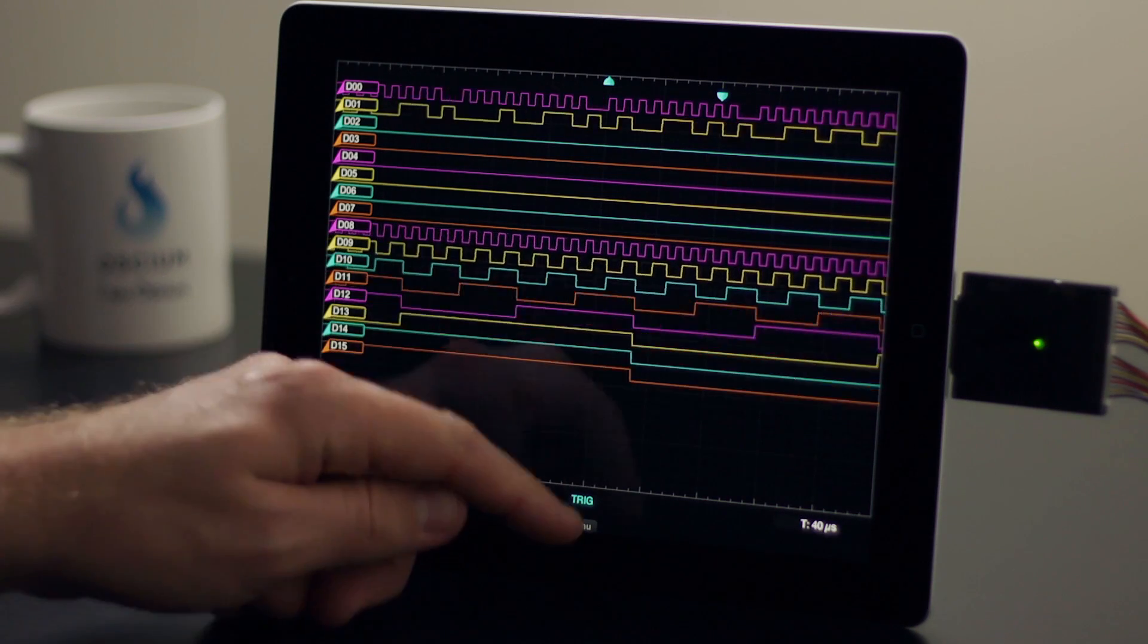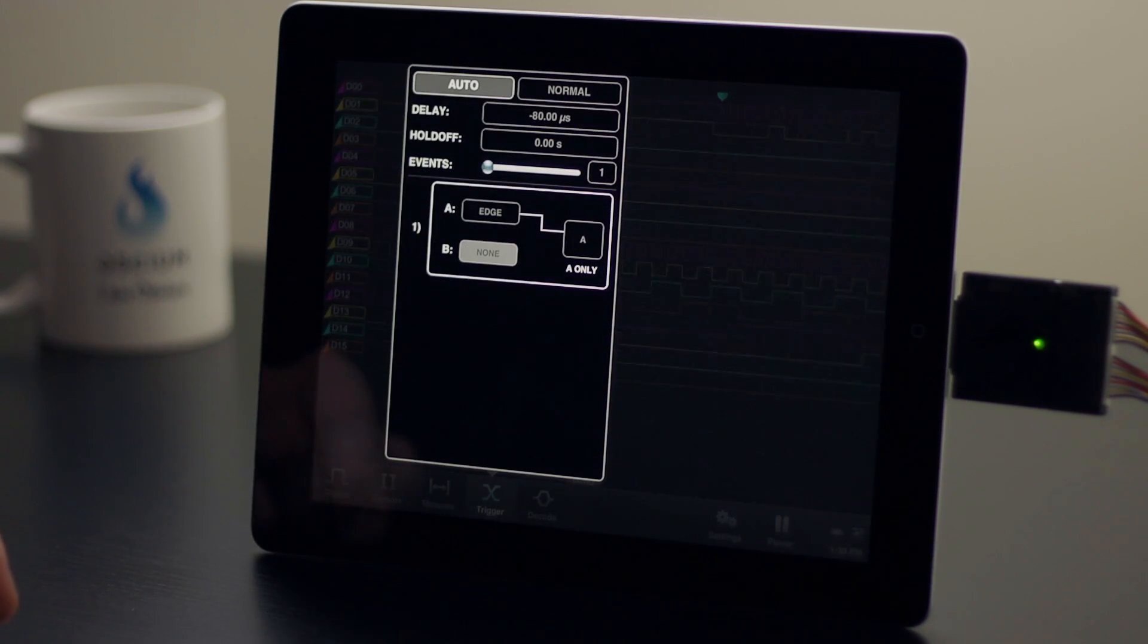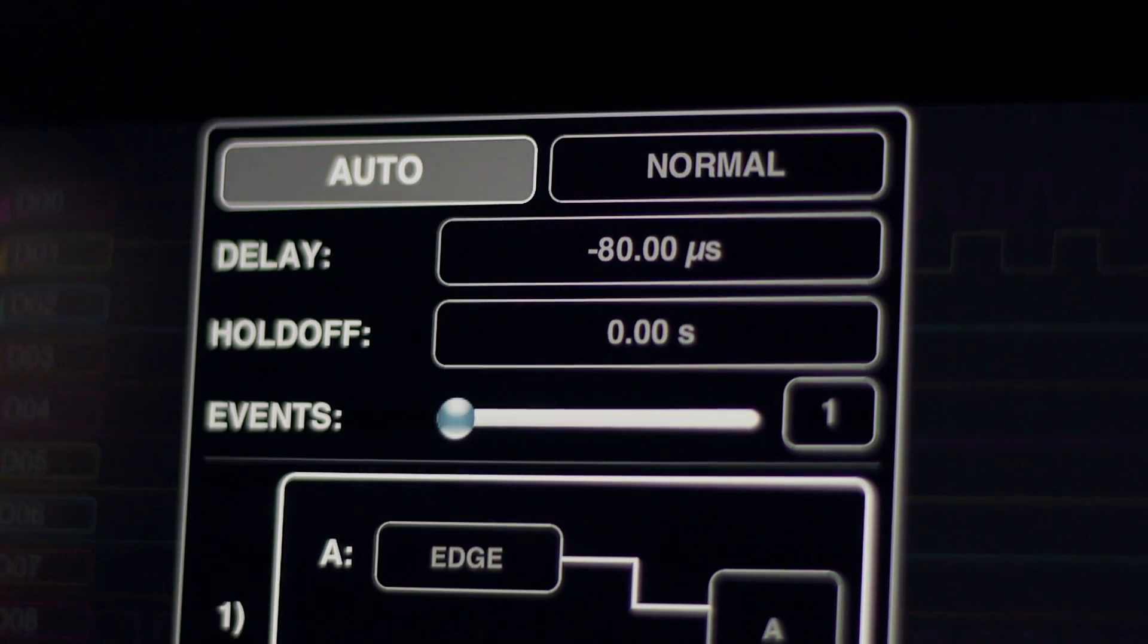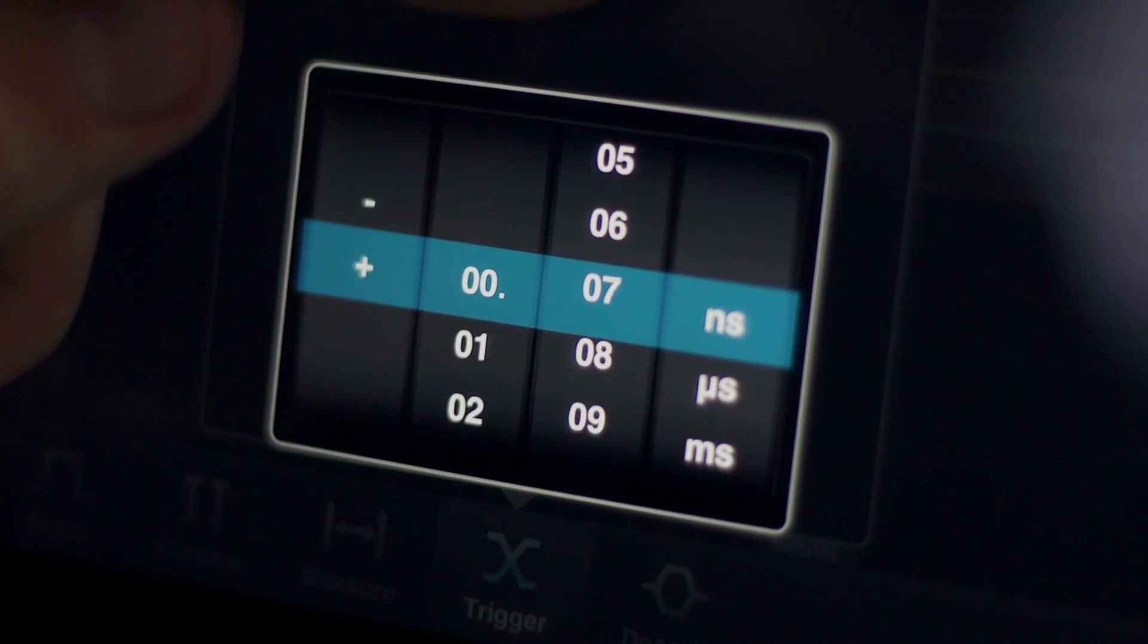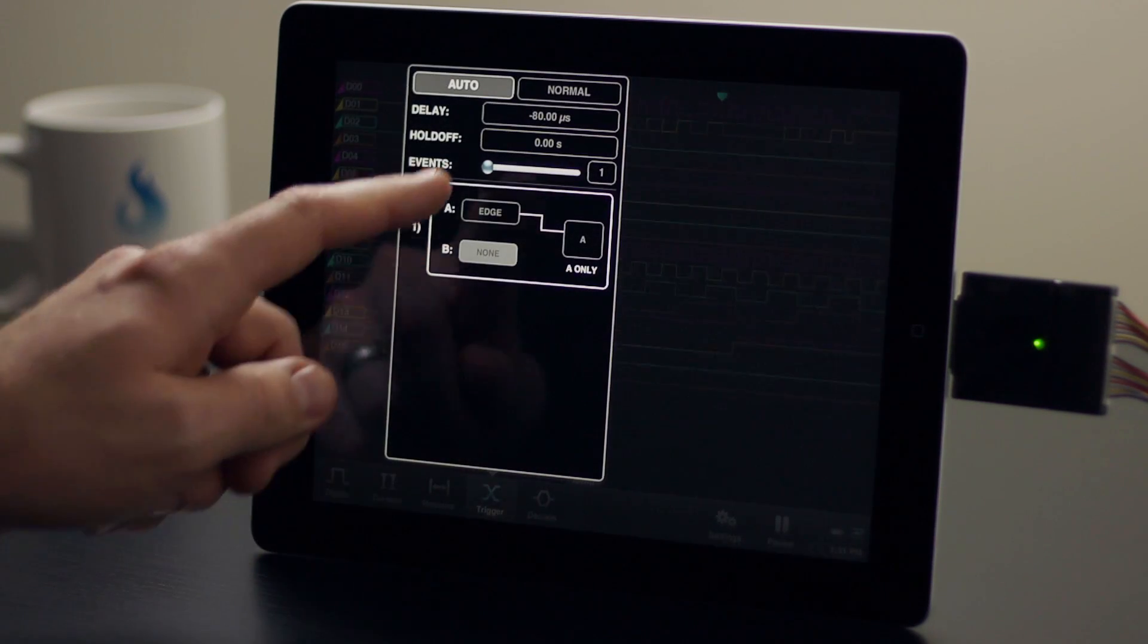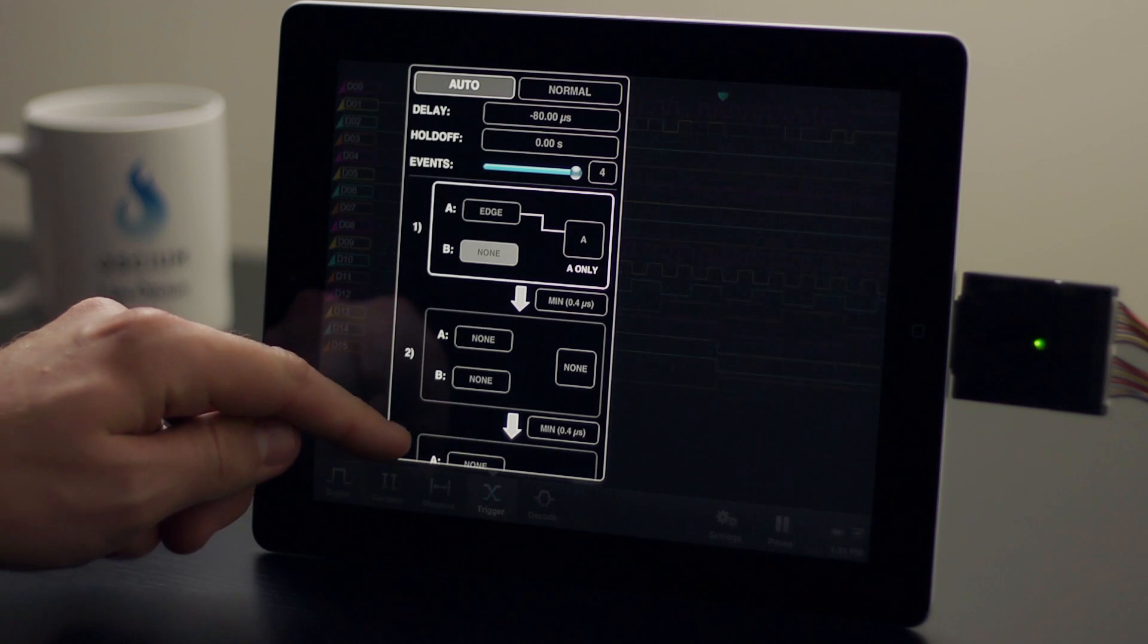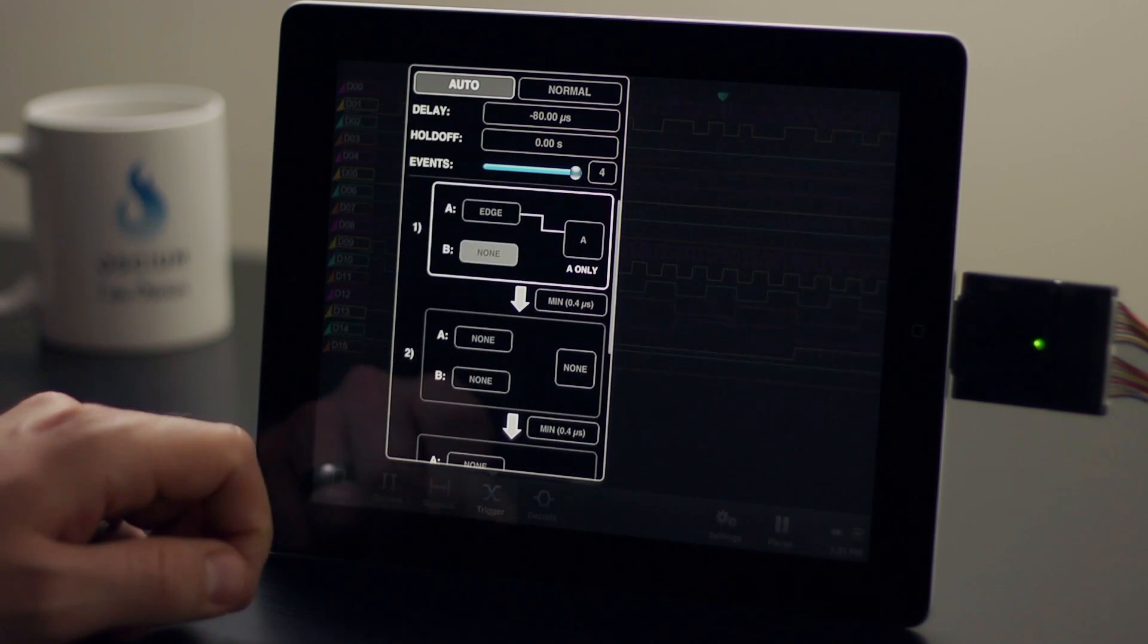Now let's take a close look at simple triggering. As we navigate the display you'll notice a few traditional oscilloscope controls like auto trigger mode and adjustable holdoff time. Trigger conditions may encompass one or up to four sequential events with adjustable delays between each subsequent event.